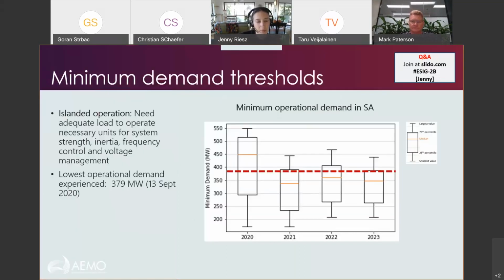Next slide. So the second issue that we've identified is just having enough load to operate the minimum units that we need, particularly when we're operating an island, as we do need to sometimes in South Australia. We need to have on a certain number of synchronous units to provide system strength, inertia, frequency control, and voltage management. Those are the essential services. And at the moment, that does require that we've got a certain amount of synchronous capacity online.